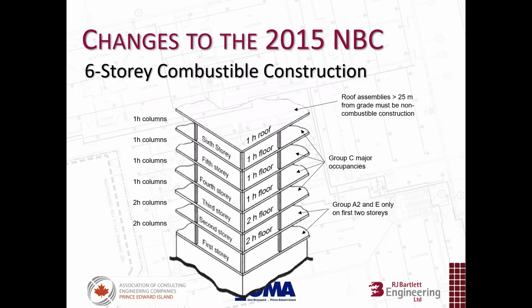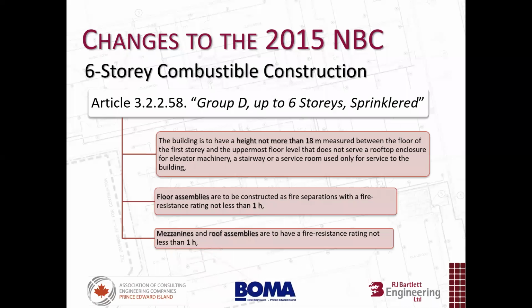Here's just a little graphic that identifies how it would look if you had A2s and Es on your first 2 stories. You would require that the floors be 2 hours, and then once you get above that 2-hour on the 3rd story, you can drop to a 1-hour floor assembly fire separation with 1-hour load bearing structure. And we notice that the roof is 1-hour rated here in this case too. So a lot of this is repeated information for the 6-story combustible construction of the office and personal services buildings, but I will just identify some of the differences.